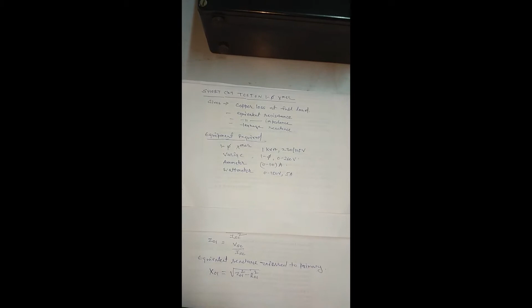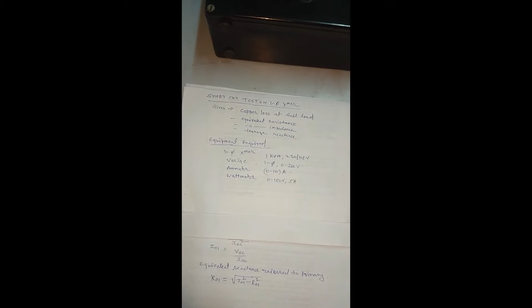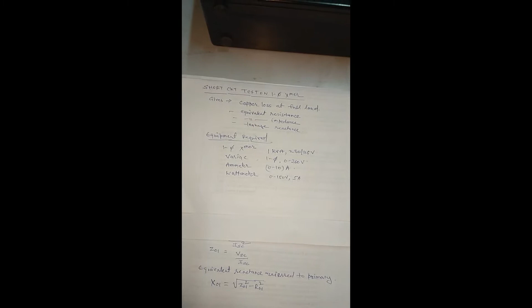This test is basically done on the HV side, and the LV is short circuited. The supply voltage on the HV side is adjusted so that full load current flows in the LV winding.